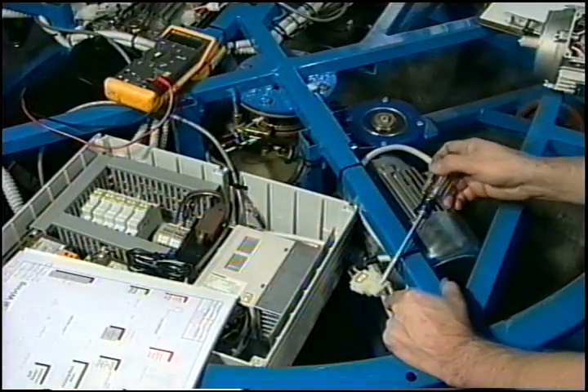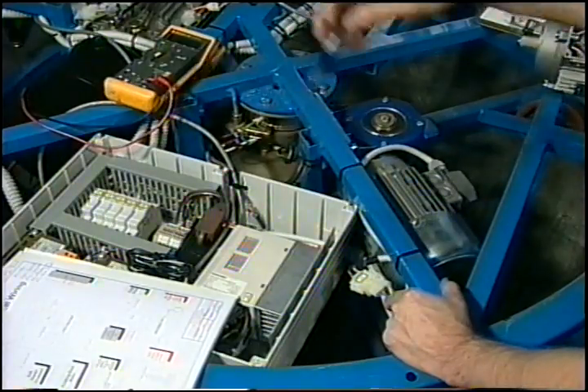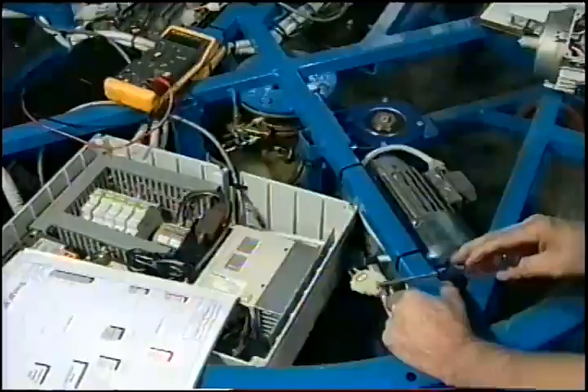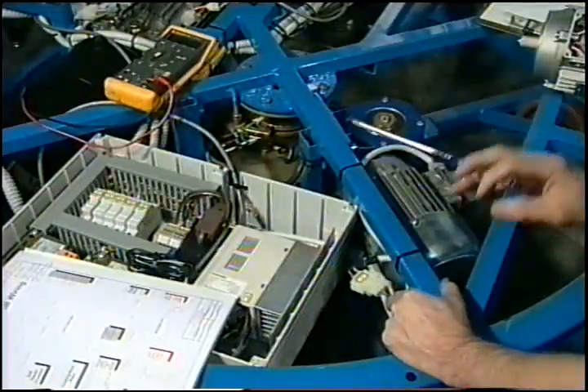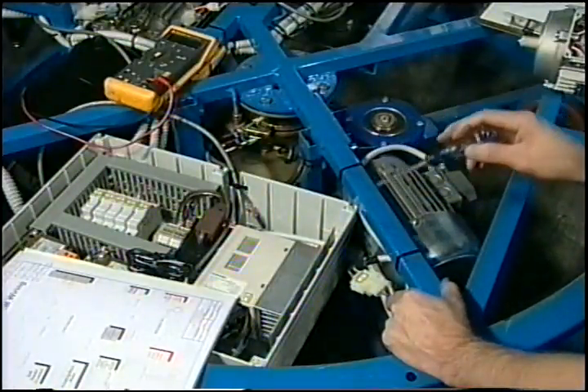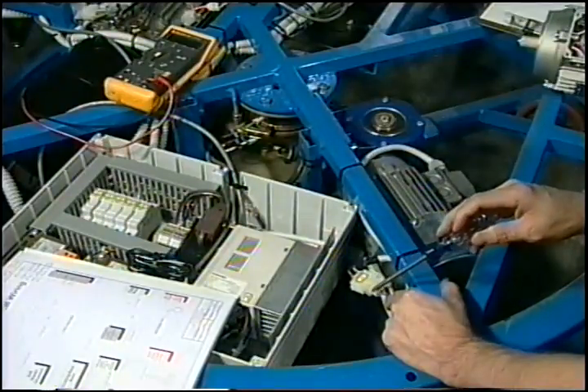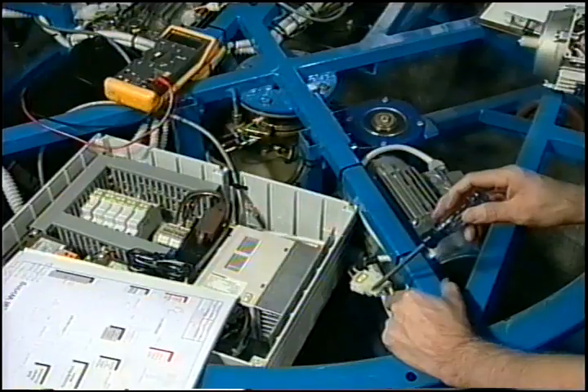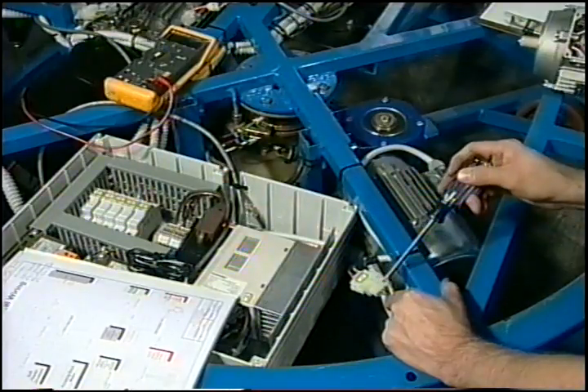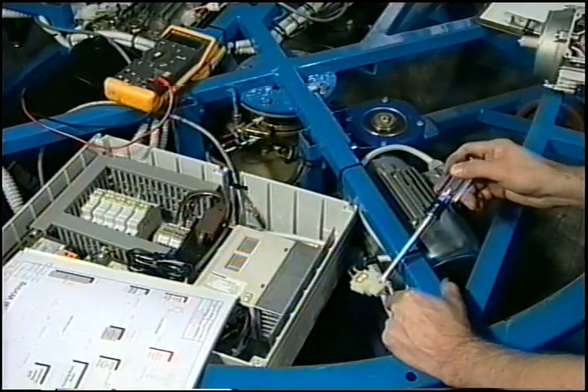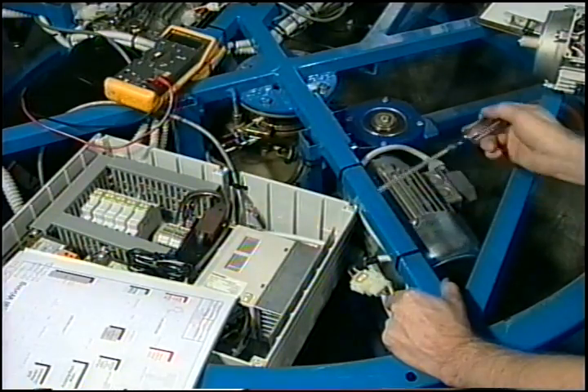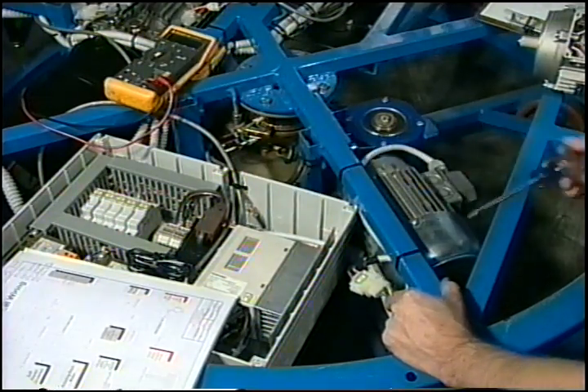Now you may not get it on all pins depending on the rotation of the ride, because the neutral line on the outside pins is always changing depending on the rotation. So if you're not reading voltage on one pin, that may currently be your neutral. Check your other 2, and if the other 2 read 170 to 180 volts AC, then that qualifies that your Toshiba inverter is operating correctly.